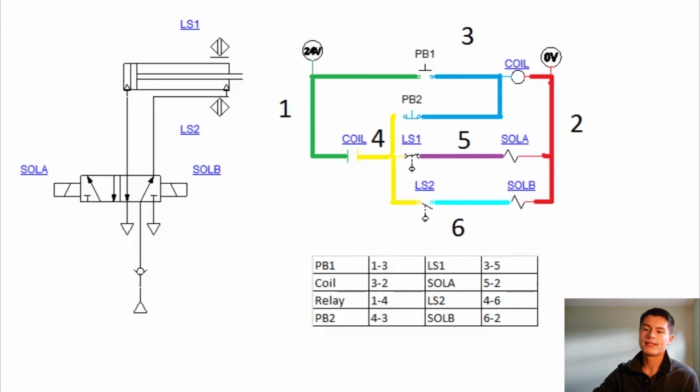And on the pneumatic side of things, first, solenoid A would be activated. That cylinder would fully extend, and then it would open up limit switch number 1, and simultaneously close limit switch number 2. Kind of confusing, but that's on the electric side. So once that's closed, it's activating solenoid B, which would flip over that 5-2 bistable valve, and that would retract your cylinder.